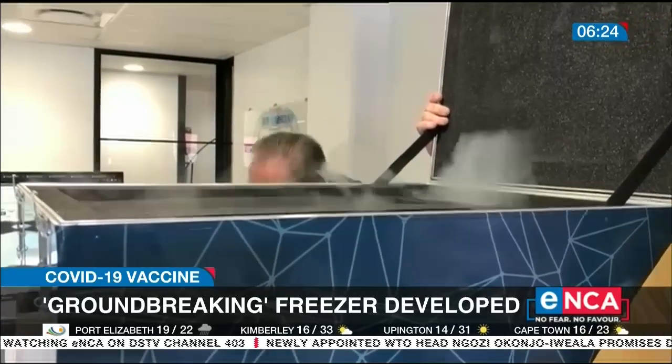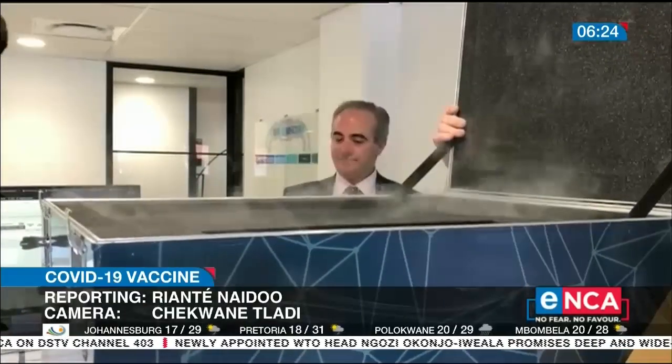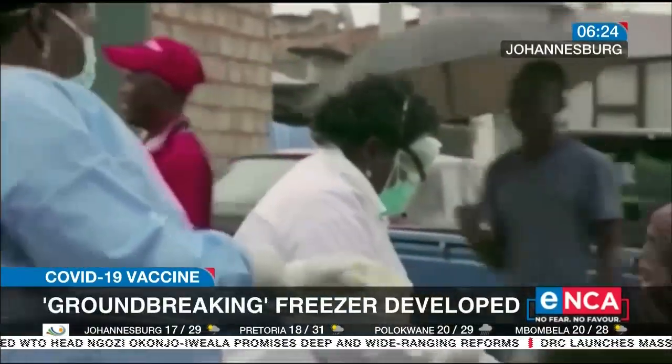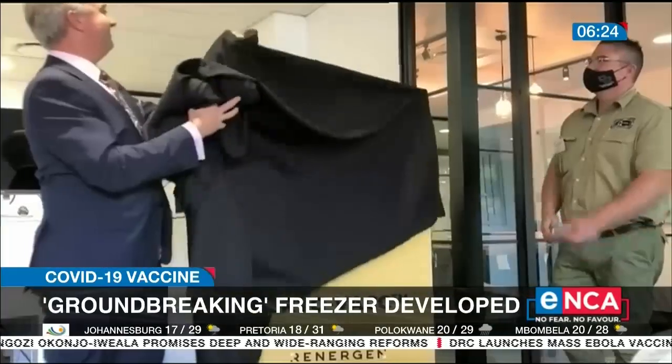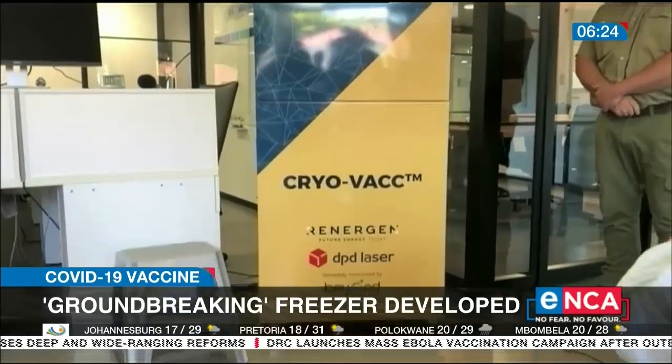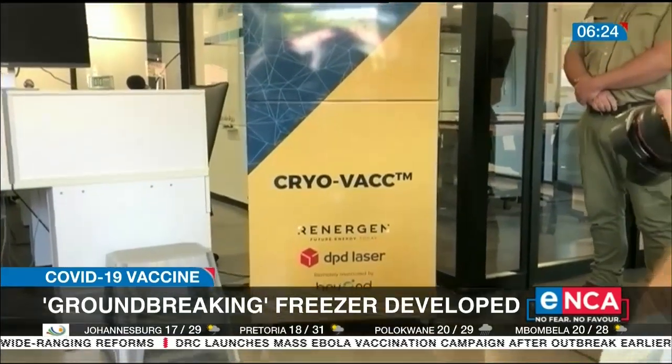It's a freezer, almost as ice-cold as liquid nitrogen, and is pegged to be the solution that will ensure the developing world can deliver world-class vaccination programs. It's called Cryo-Vacc. The Cryo-Vacc can operate from minus 150 all the way up to 8.